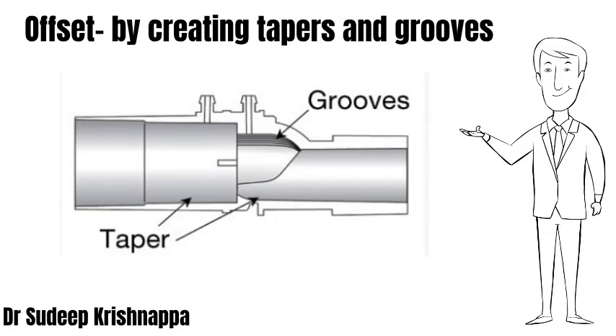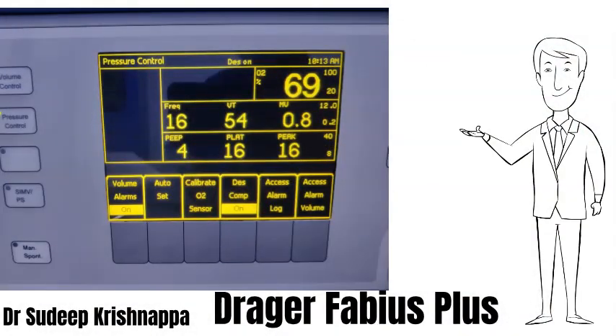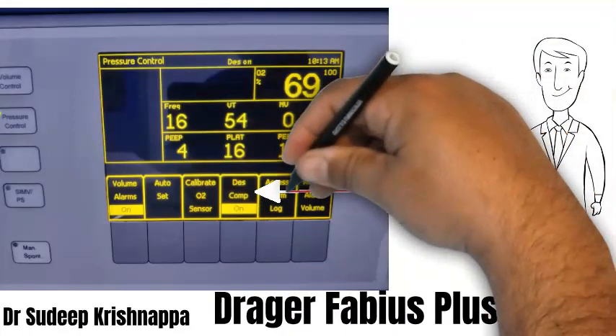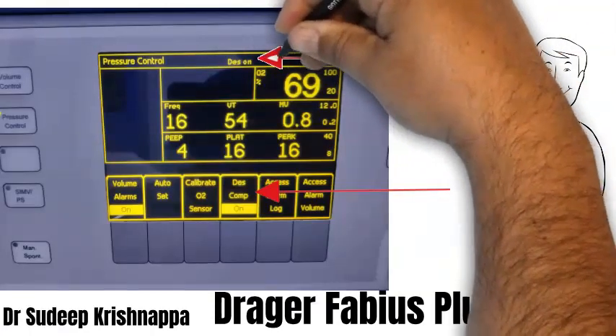As Drager machines use a hot wire anemometer, when desflurane is used in some of the older workstations like Fabius and Fabius Plus, some inaccuracies in flow measurement can creep in. This is because desflurane is heated to a temperature of 39 degrees and is added in a significantly larger proportion compared to other inhalational agents. Both of these factors can alter the temperature of gases flowing in the breathing circuit, which in turn can affect the temperature drop at the anemometer, thereby causing variations in flow measurement.